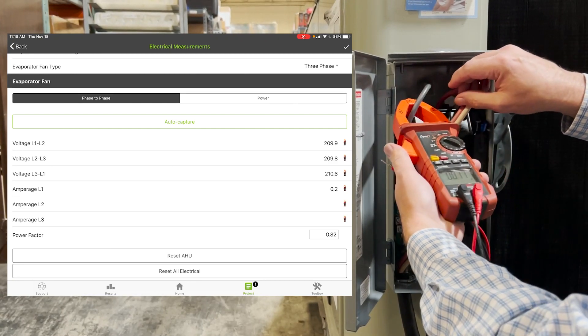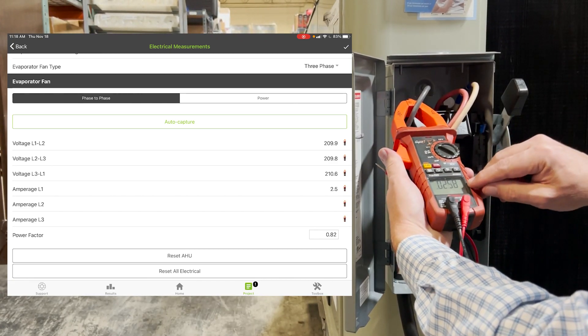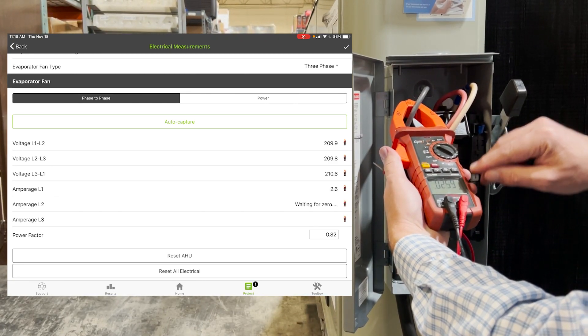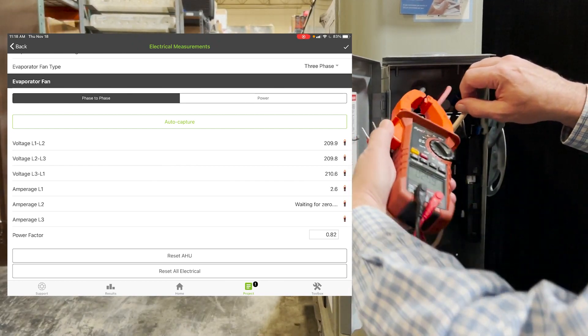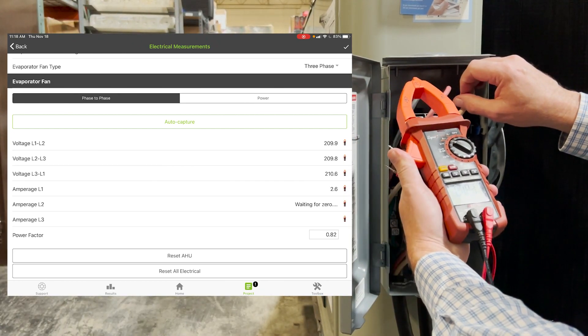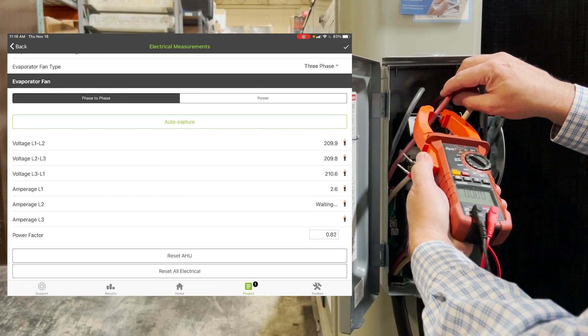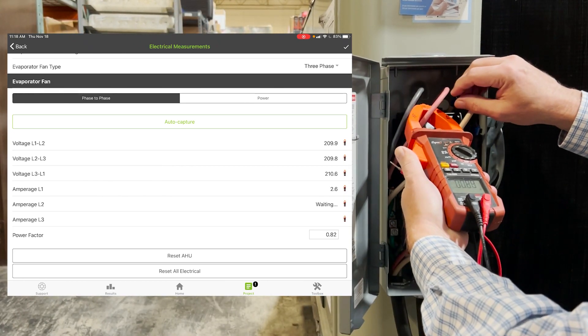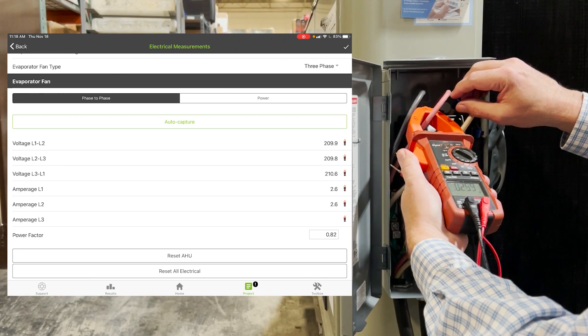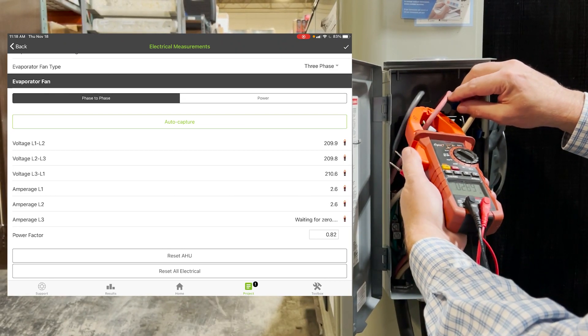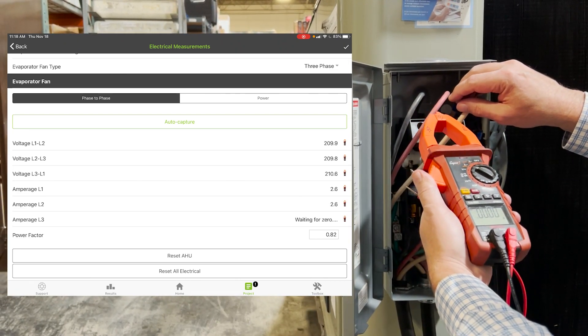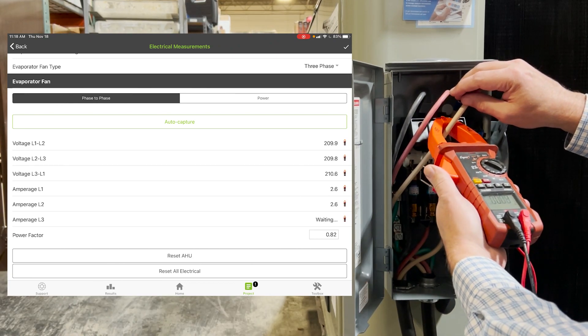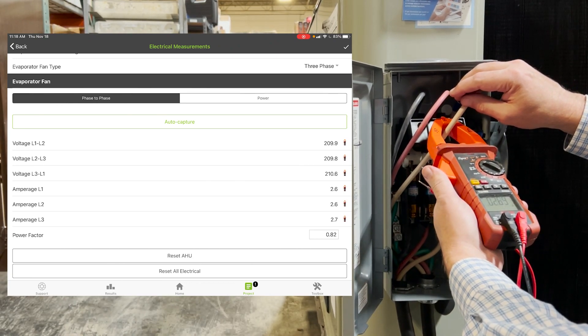Now, the small delay is for the meter to stabilize, so we can sense the voltage stabilized. Now I'm just going to move it over to amps, and when I move it over to amps, I'm just going to go L1, L2, L3. So again, I'll clamp it around. You'll see our amp draw come up, stabilize, take it off. It's got to go back to zero. Put it on L2. Pull it off. It's got to go back to zero, and then L3.